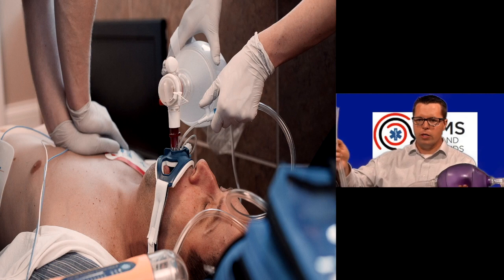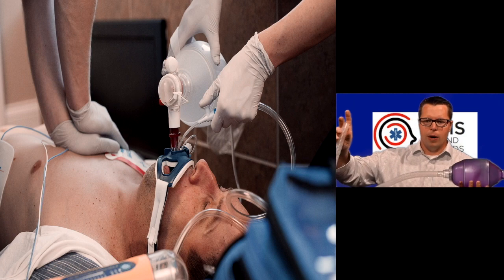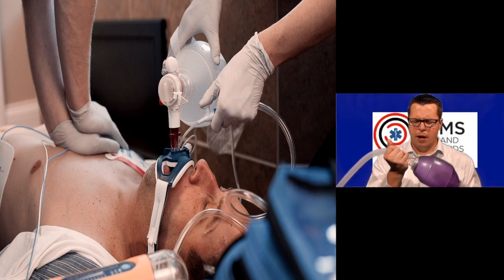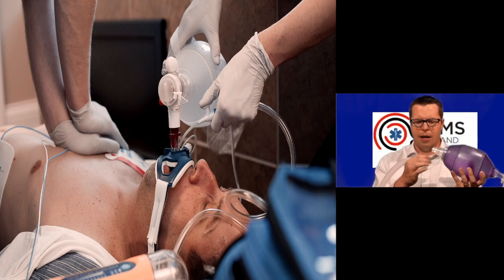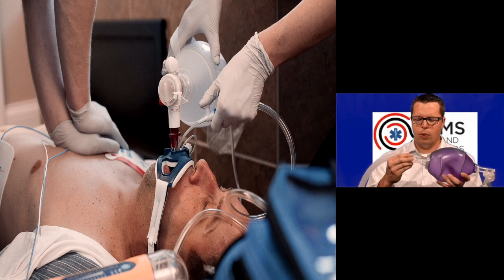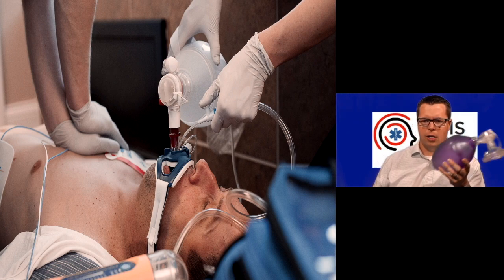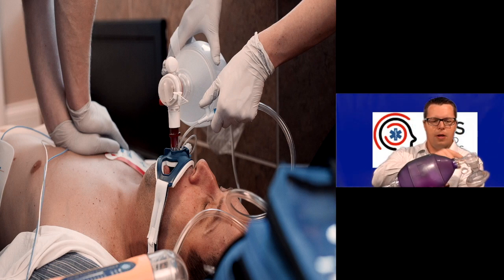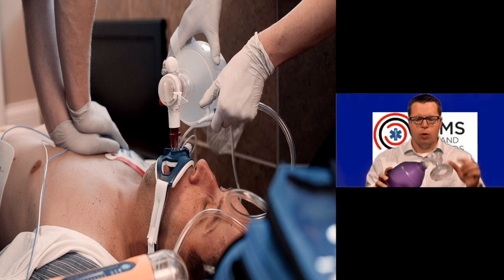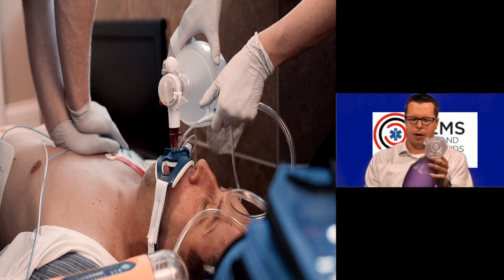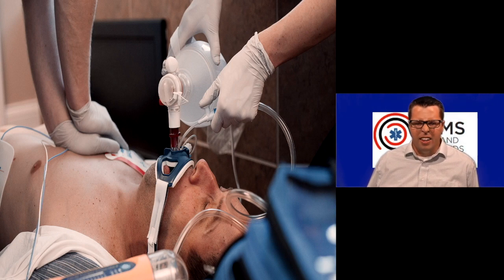So again, if you squeeze it right now, it's drawing in room air from the back rather than drawing in oxygen. If you hook oxygen tubing up to it, the oxygen actually meets right here and then, again, backfills through this reservoir tube. So that's the way that this style of bag works. It still works on the same principle in that you draw air or oxygen in from a reservoir, you deliver it through a one-way valve here, which in this case is the duckbill, and then when air tries to come back out, it'll be forced back out through the exhalation port, and in this case, the PEEP valve might fit right there on that thing.